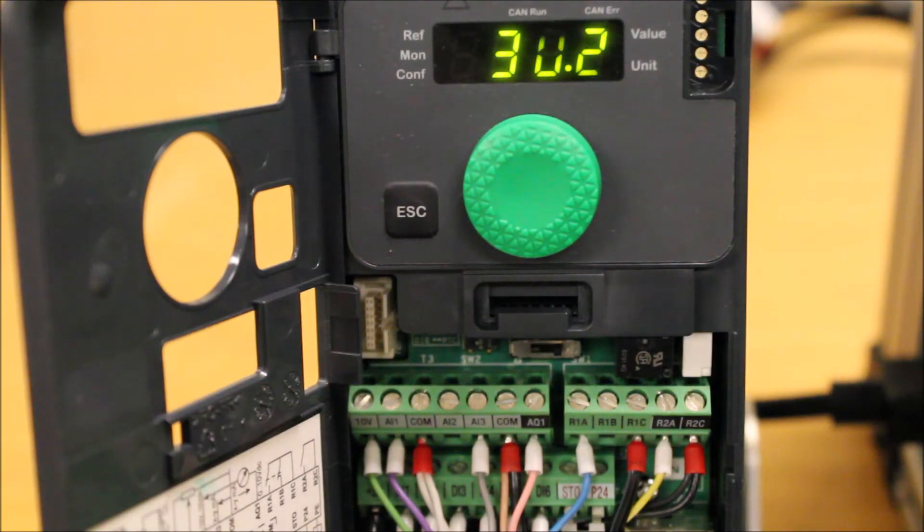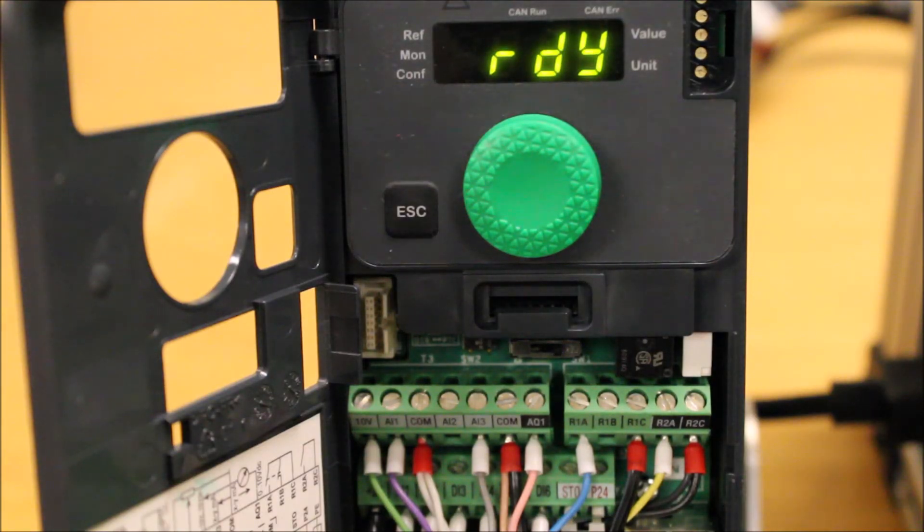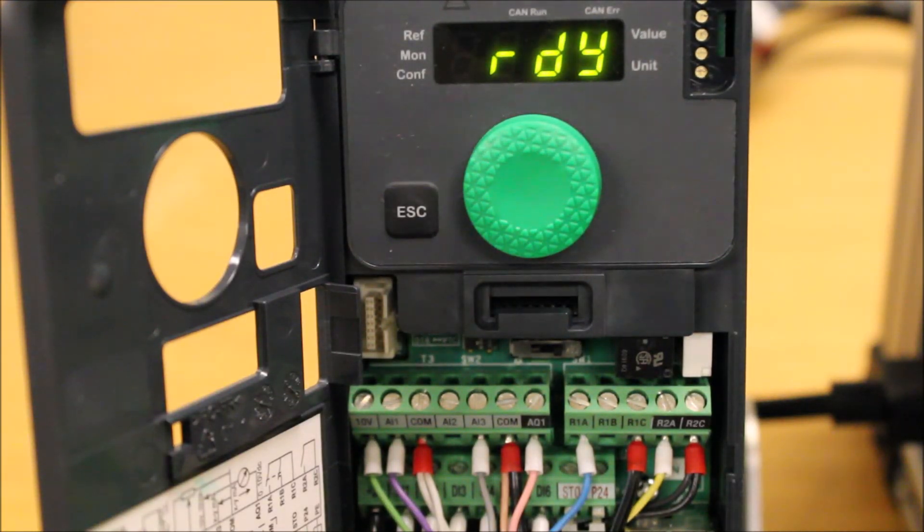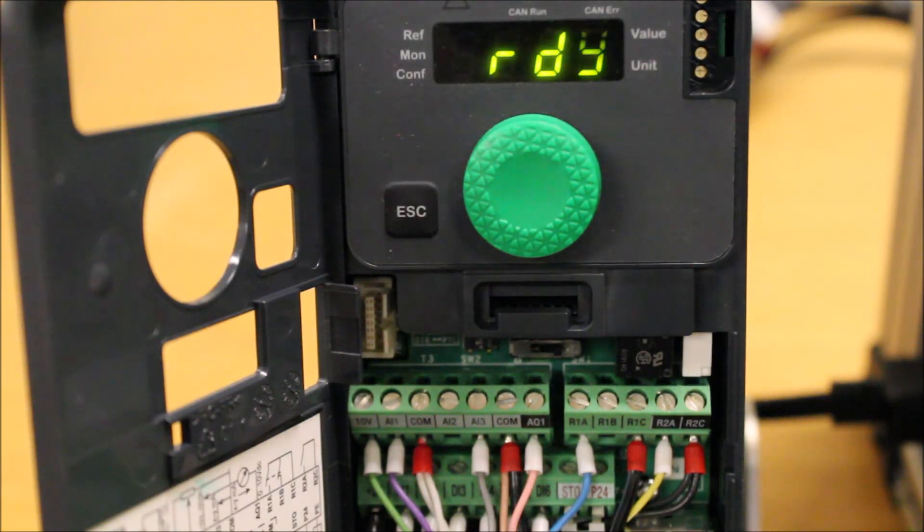That hopefully will help you determine how to program this particular function. Keep in mind that you can program the presets as network commanded functions as well, so you can assign a particular bit to be a preset. But this particular video only shows you the one where you assign a terminal, DI3 and DI4 as an example, for a preset speed functionality on the ATV320 drive.